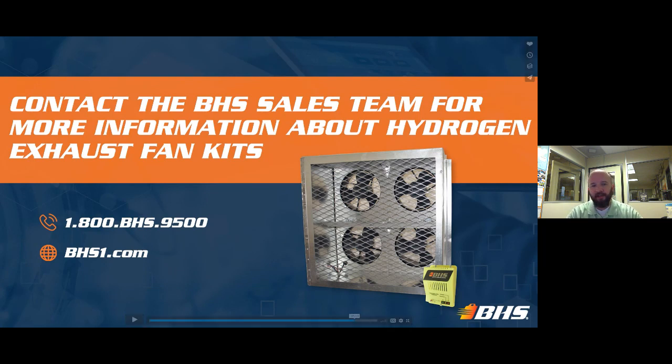With the hydrogen exhaust fans, it's going to depend on the local municipality or regulations that are in place, but it's important to know to have dampers to stop airflow from going out of the building when the fan is not working. This one also includes what we call in the States a fireman disconnect. If for any reason a fire alarm is tripped, there's an additional circuit on this fan that can be activated that closes the fan off so it is not able to let air flow back into the building, which would feed the fire itself.